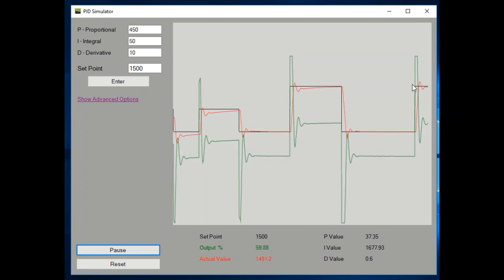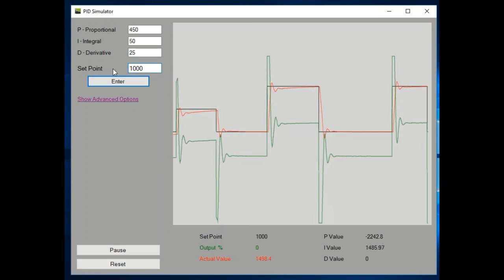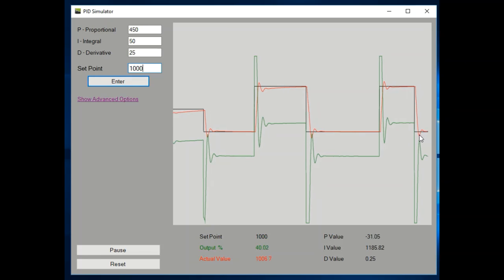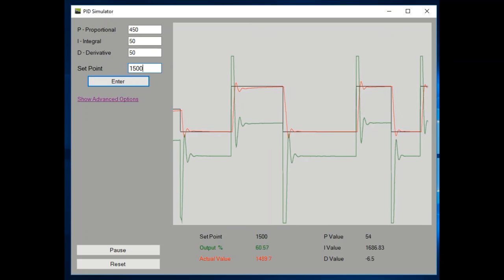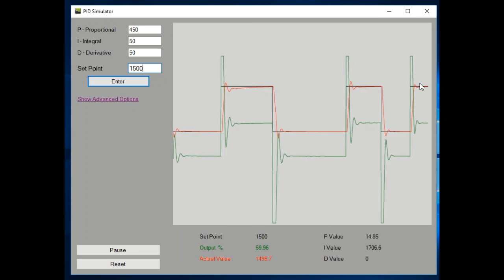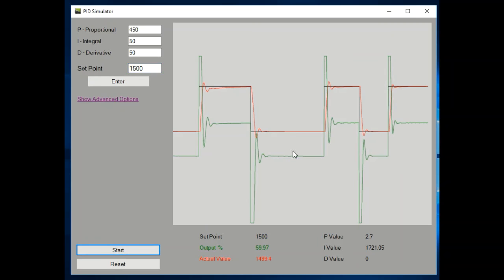We added a bit of derivative — we still have an overshoot, so let's increase that more. Much better, but still a bit of an overshoot. Increase it again. Now that is a very stable, fast acting and accurate controller with very little overshoot. We can increase the derivative a little more to see if we can bring that overshoot right down to nothing, but the issue is if you go too high it can actually cause your controller to become unstable. Or if you have distortion in the system, the derivative is going to do the opposite of what you want. So be careful tuning the derivative — bring it to a reaction time and stability that works for you without causing negative effects.